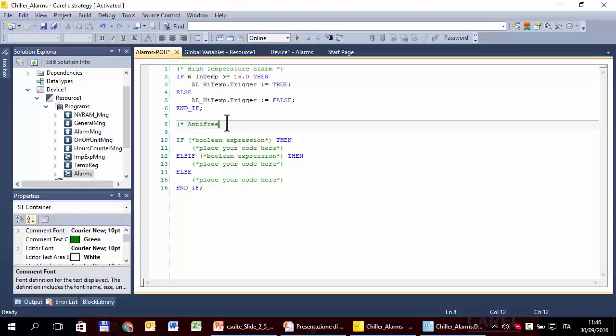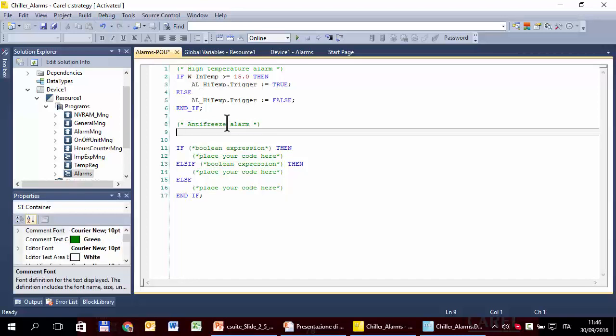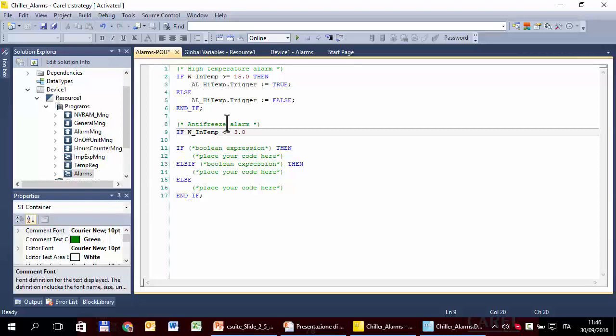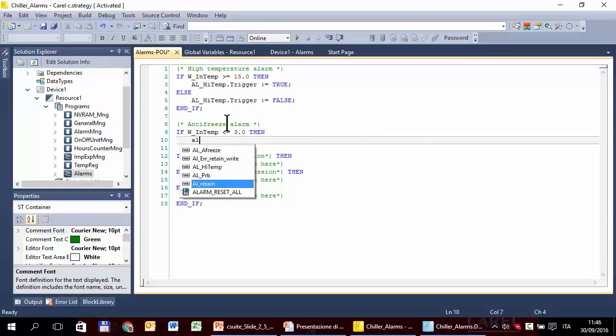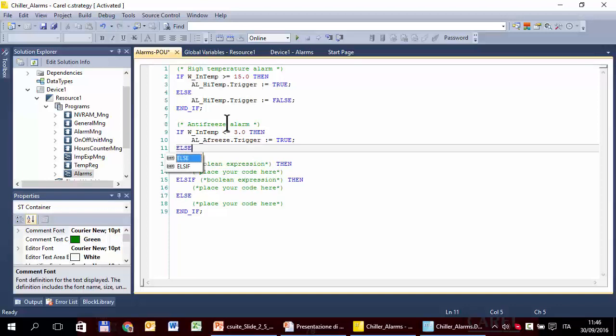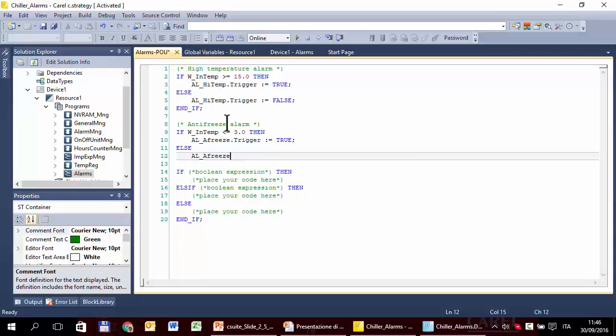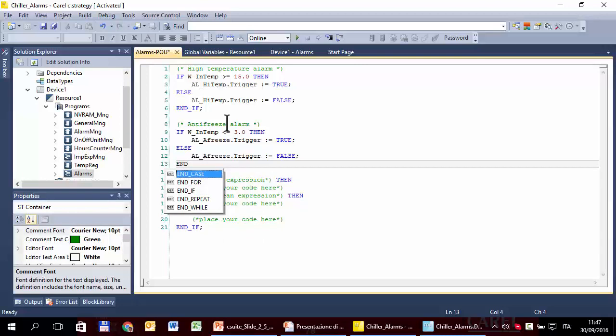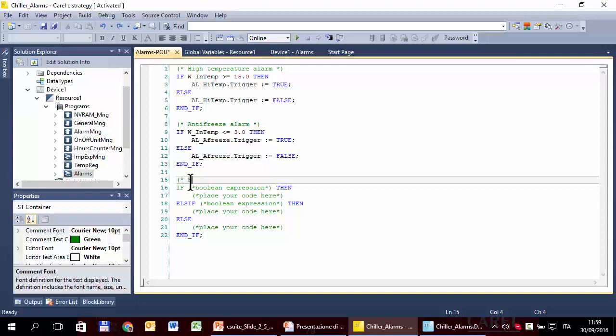The next alarm is antifreeze, which is very similar. I prefer to write it again from scratch. IF temperature <= 3 THEN antifreeze.trigger := TRUE; ELSE antifreeze.trigger := FALSE; END_IF.